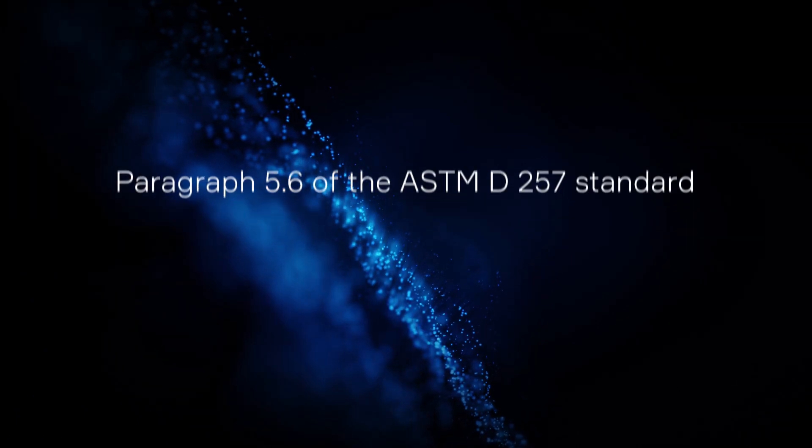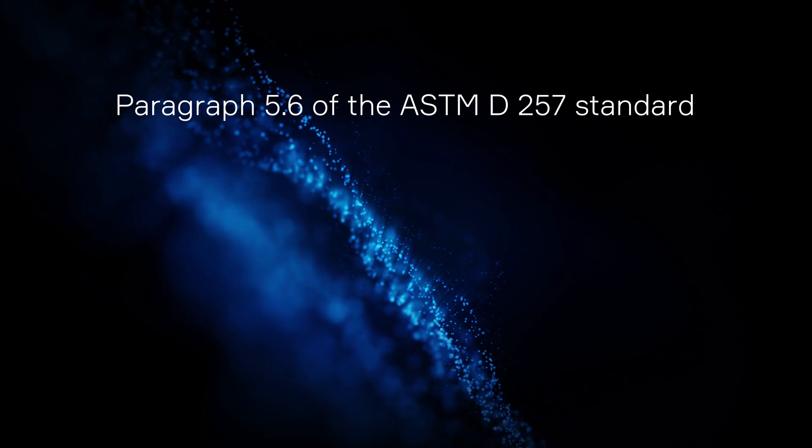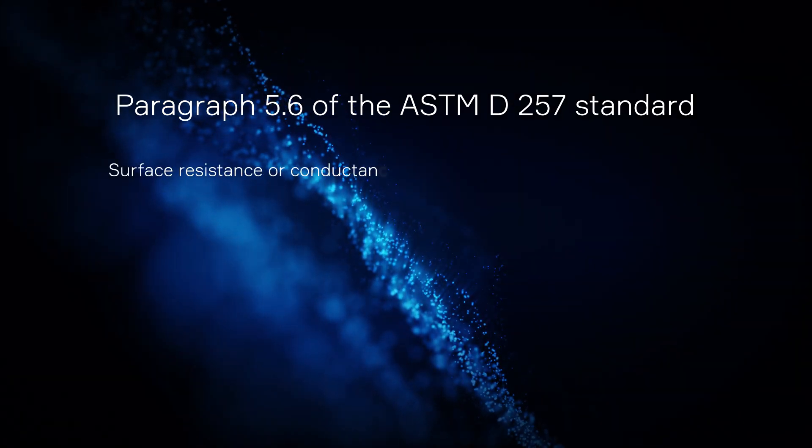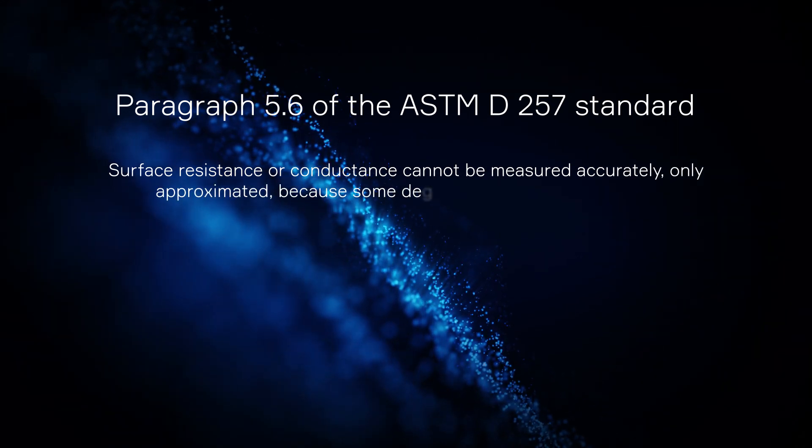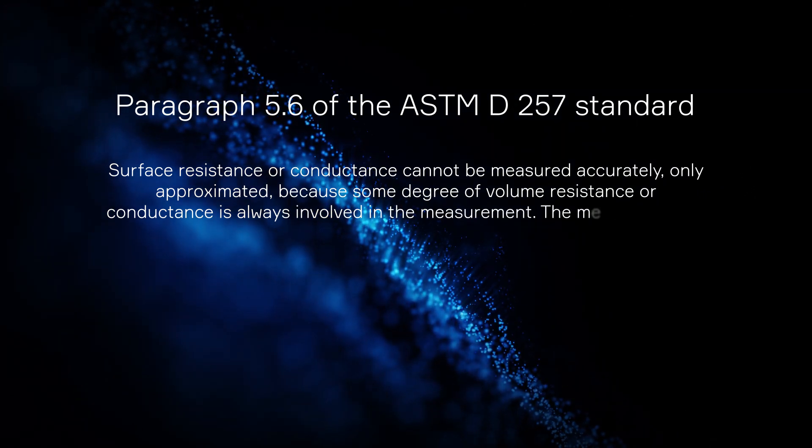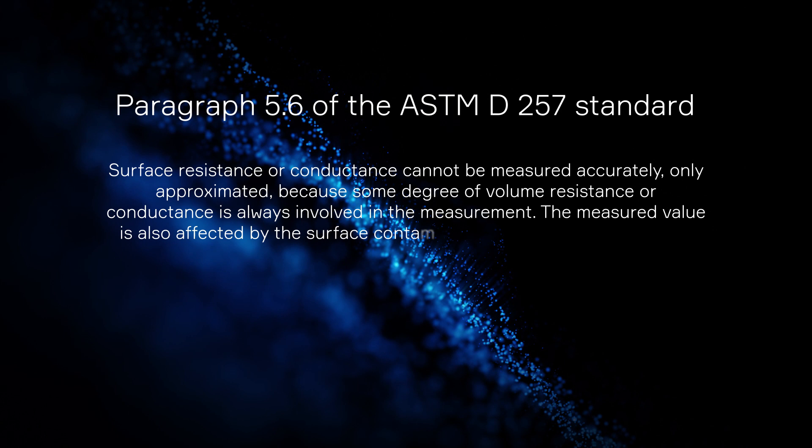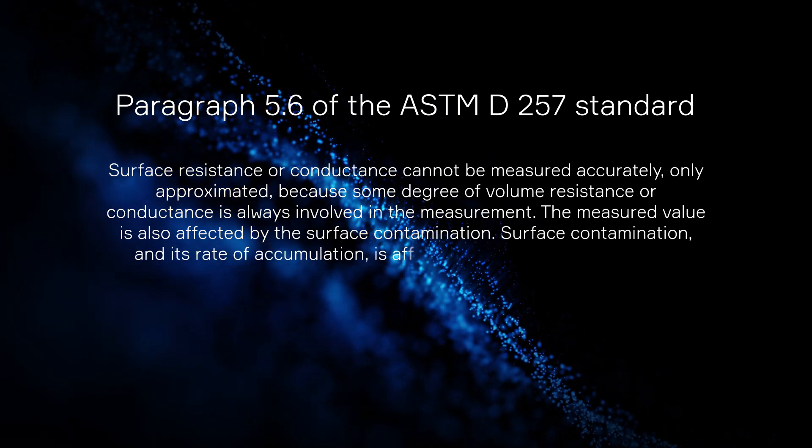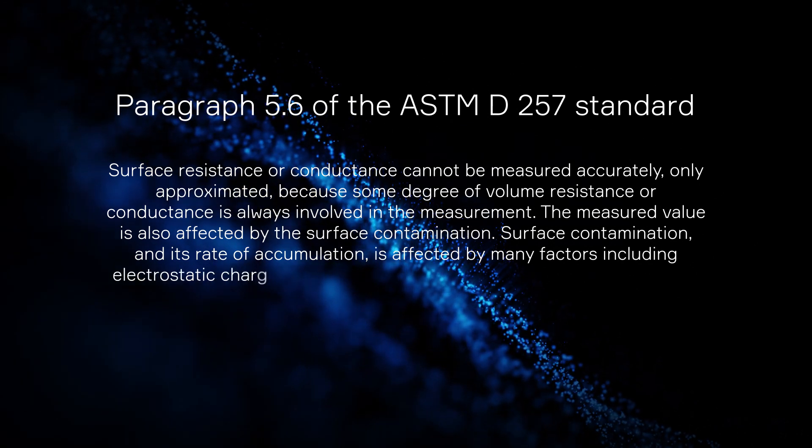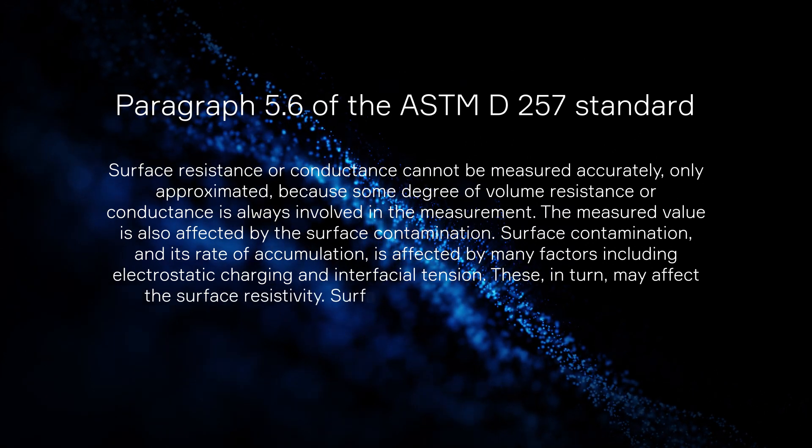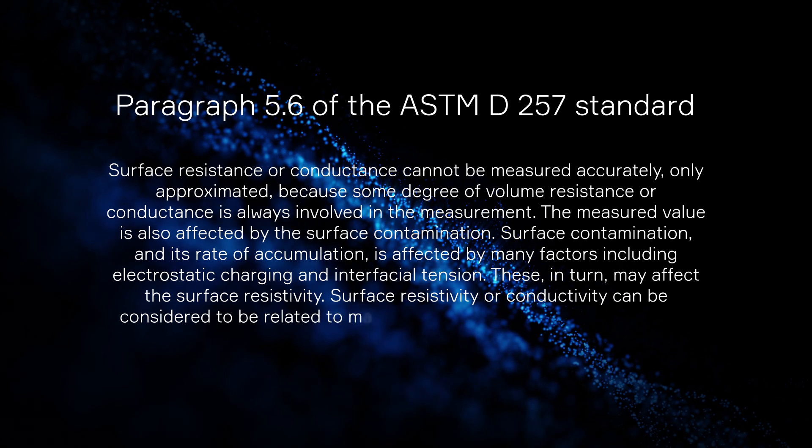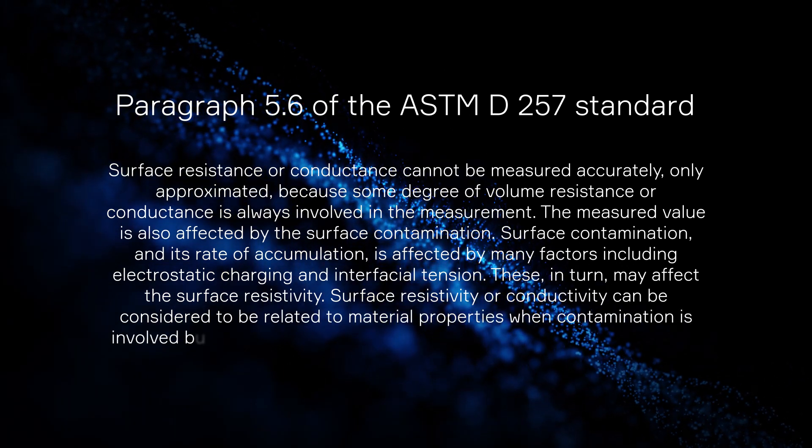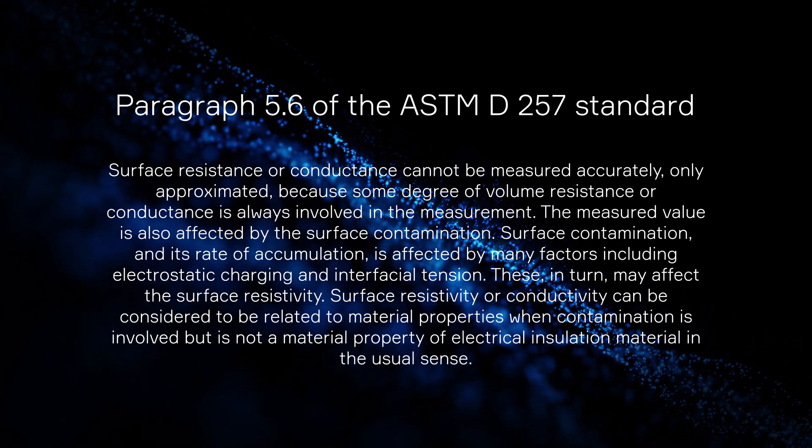The essence of surface resistance measurement is described well in the ASTM D257 standard, which says surface resistance or conductance cannot be measured accurately, only approximated, because some degree of volume resistance or conductance is always involved in the measurement. The measured value is also affected by the surface contamination. Surface contamination and its rate of accumulation is affected by many factors, including electrostatic charging and interfacial tension. These, in turn, may affect the surface resistivity. Surface resistivity or conductivity can be considered to be related to material properties when contamination is involved, but is not a material property of electrical insulation material in the usual sense.